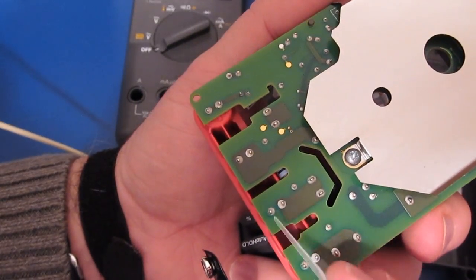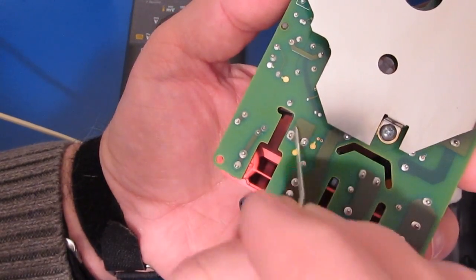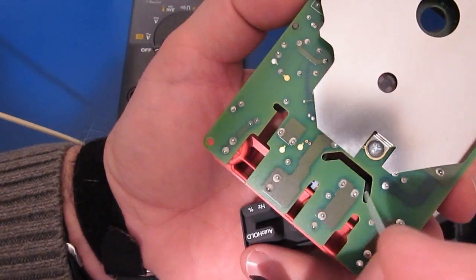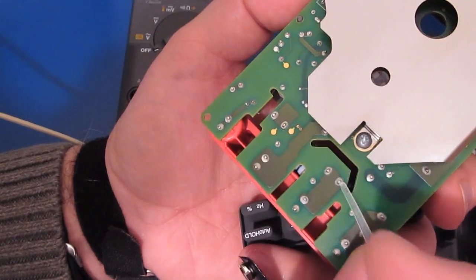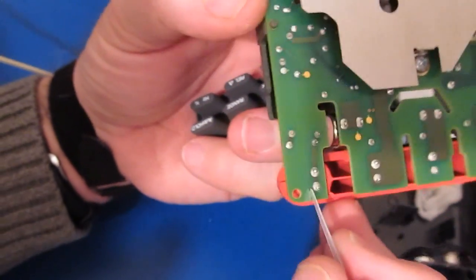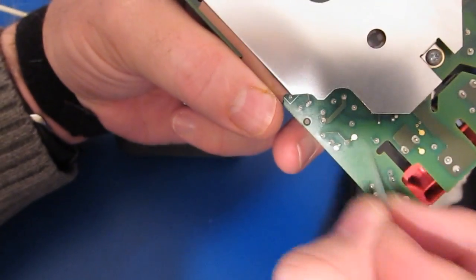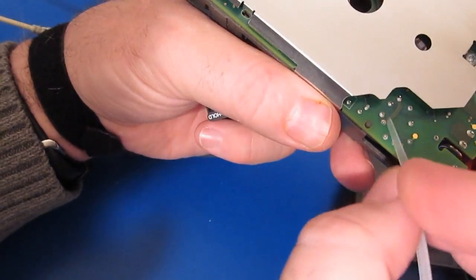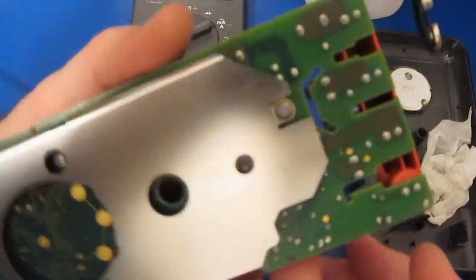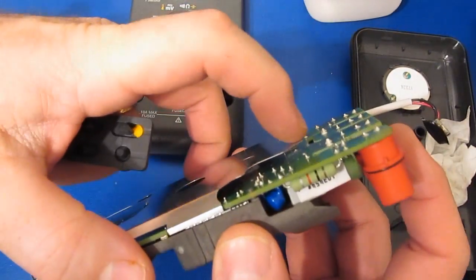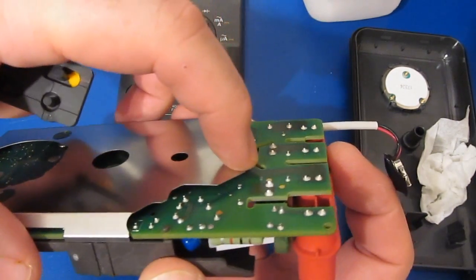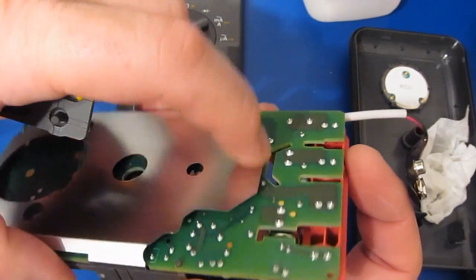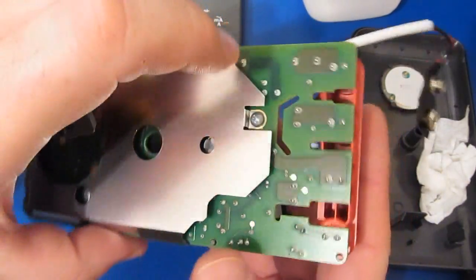Our second current input is right here, and of course there's a fuse across these two points. But again you've got this nice slit cut in here, so I don't see any way for it to arc from here to here. On the far left side is our normal volt-ohm input, and again we have the PTC sitting here and our high voltage resistors up in this area, and our MOVs are right in this area. In the picture the person sent me it looked like the shield was bent down, but even if that's the case, you'd really have to bend this over, and I still don't know if you could get it to arc between any of these pins going back to the shield. So I don't see any problems with that.